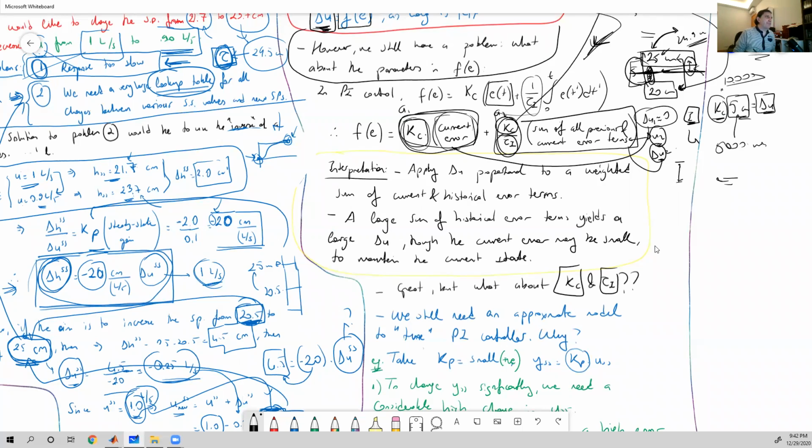But there is one very important difference compared to model-based control. In model-based control, this model should be perfect if you would like to obtain no offset, right? This 20 should be really exactly 20, because everything we compute depends on that value. On the other hand, let's say that the optimal value of Kc, and I'll try to explain what optimal is, is 12.5 or whatever the unit is. Instead of that, if you write 10 or 15, most likely the process will still converge to the set point. Maybe it's going to be a suboptimal trajectory, yet the control action will still work fine.